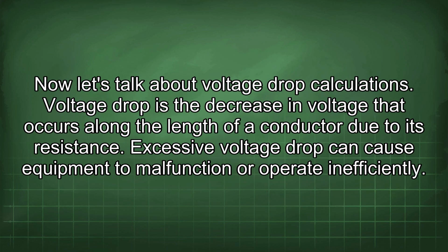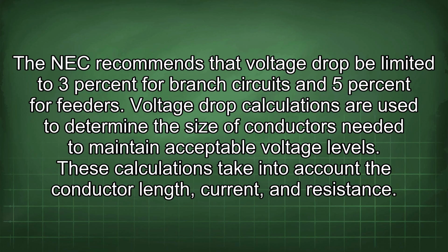Now let's talk about voltage drop calculations. Voltage drop is the decrease in voltage that occurs along the length of a conductor due to its resistance. Excessive voltage drop can cause equipment to malfunction or operate inefficiently. The NEC recommends that voltage drop be limited to 3% for branch circuits and 5% for feeders.